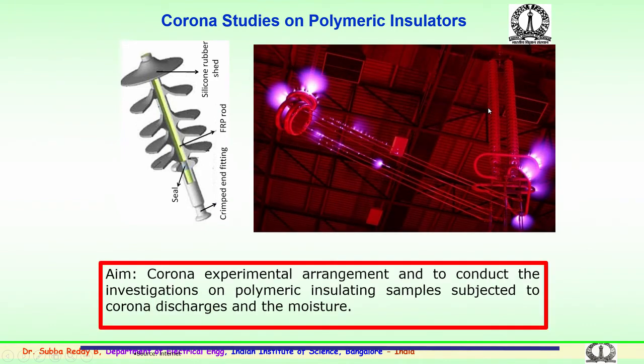So, the first thing we would like to focus on is the corona aspects, the corona studies on polymer insulators. As mentioned earlier, just for information, a polymer insulator mainly comprises crimped end fittings, with the end fittings on both sides. Apart from that, we have a fiberglass rod, an FRP rod, running from metal to metal, and silicone rubber or polymeric sheds which are housed on the insulators.